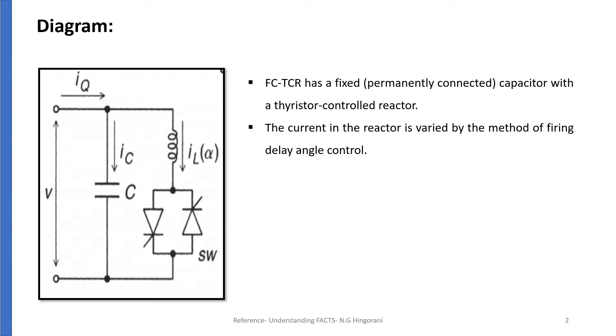FCTCR is a basic VAR generator arrangement using a fixed, i.e. permanently connected, capacitor with a Thyristor Controlled Reactor. The current in the reactor is varied by the method of firing delay angle control. The fixed capacitor in practice is usually substituted fully or partially by a filter network that has the necessary capacitive impedance at the fundamental frequency to generate the reactive power required, but it provides a low impedance at selected frequencies to shunt the dominant harmonics produced by TCR.